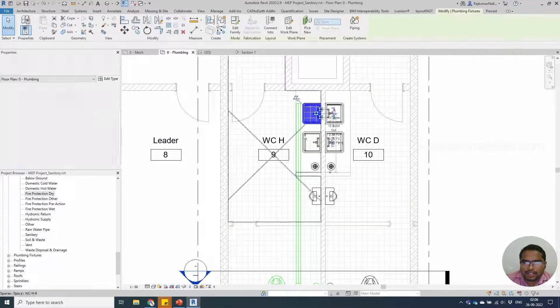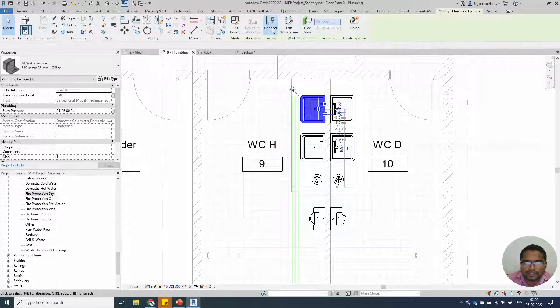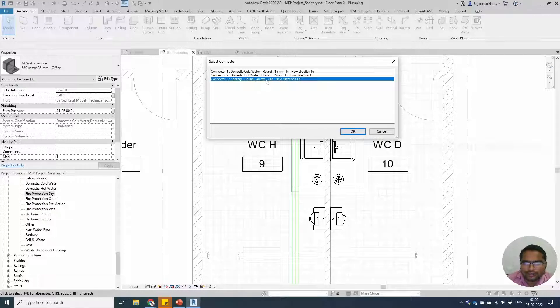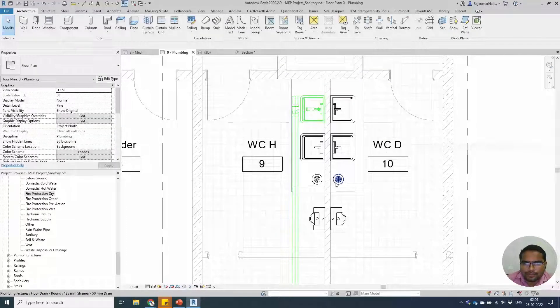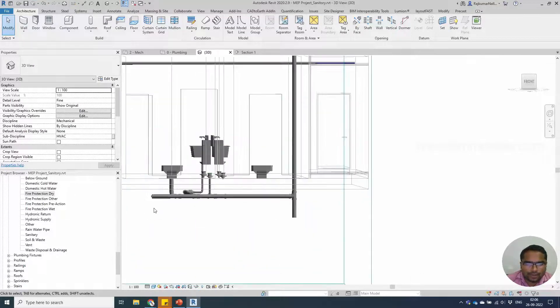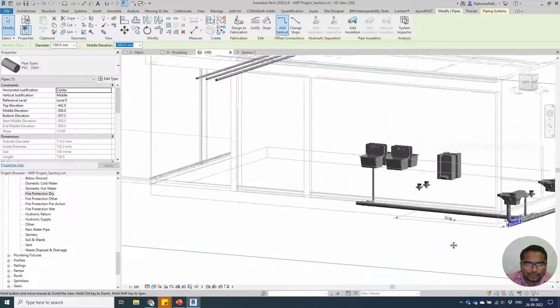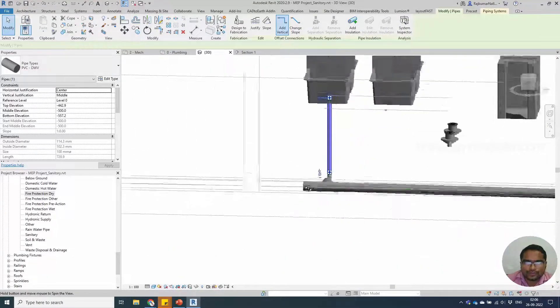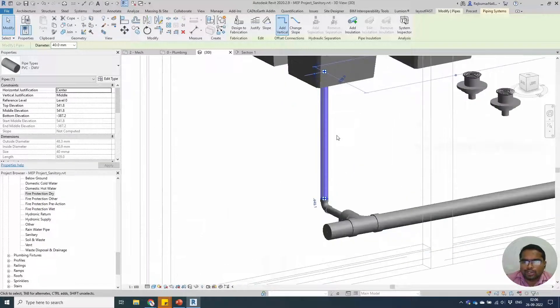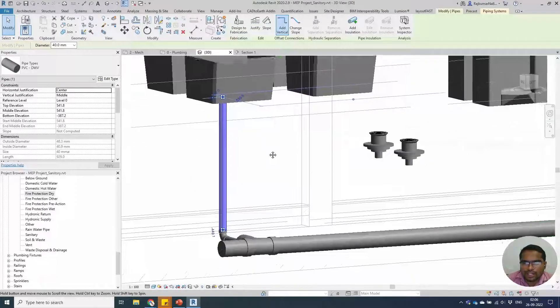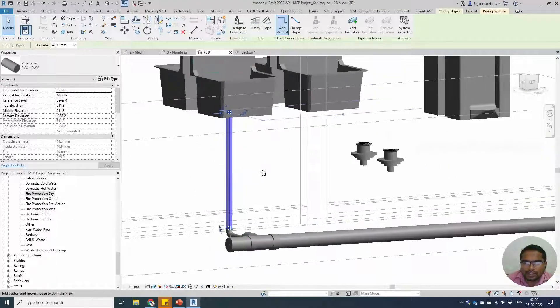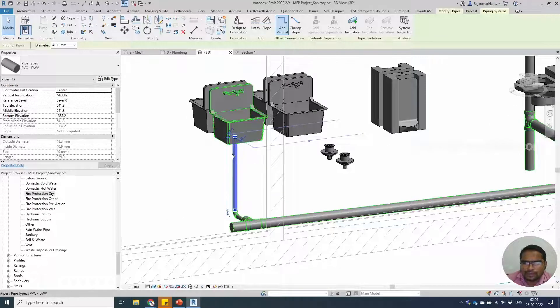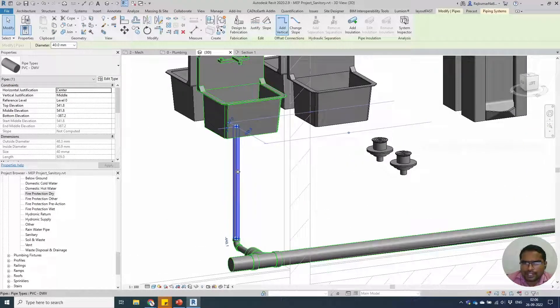Select the equipment or the fixture, say connect into the pipe which we are trying to connect, this 40 millimeter sanitary system. I'm checking that in 3D whether it is connected properly. Yes, it is. But do remember, we have to connect to a sanitary system which needs to be a U-trap or S-trap that depends on the system requirement.